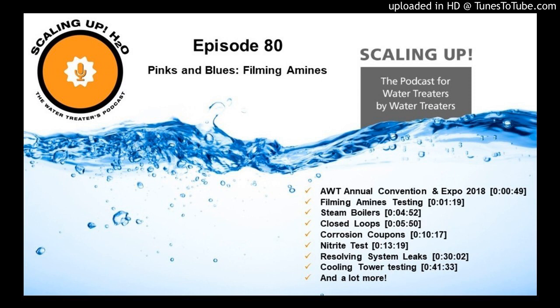But we here at Blackmore Enterprises have had very good results, but we're also very intentional in how we use the product. So filming amines, if you are not familiar with how filming amines work, they basically coat the entire surface that you are trying to protect, and anything between the filming amine and the wall interface, it is going to clean off of the systems.